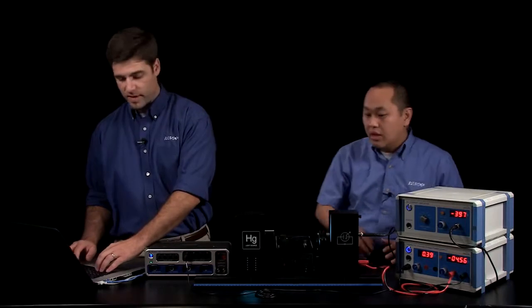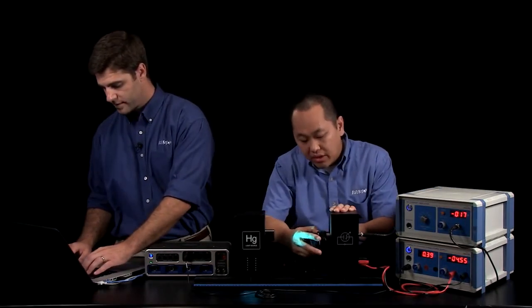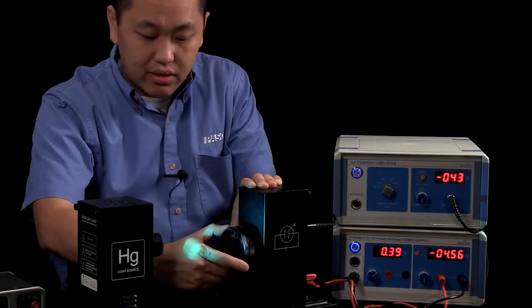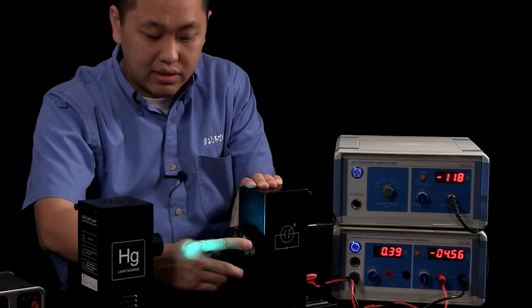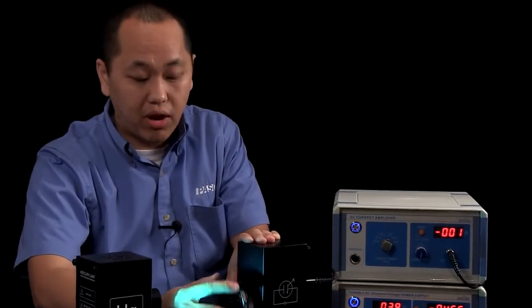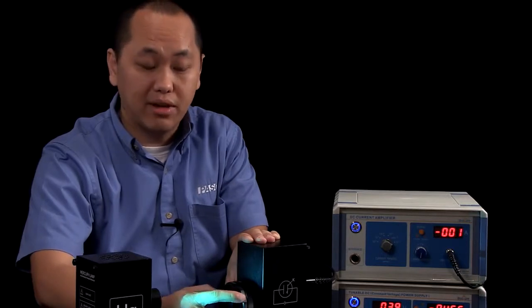Chong can you read me those values? Yeah. The first one is 365. And these values are going to be in nanometers. 405, 436, 546, 577. And there is one additional setting which is zero which blocks out the whole opening itself. And then I'm going to move it back to 365.